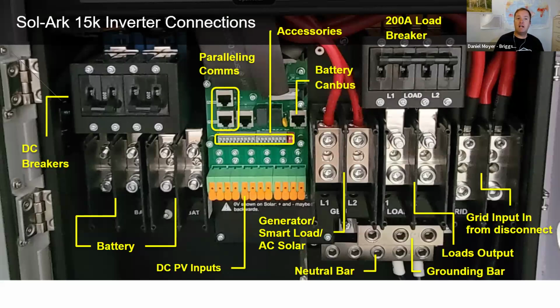On the left-hand side, we have our DC breakers. What's really cool about that Sol-Ark 15K is that we have dual battery inputs, which means that if you're going to have a single stack of our batteries, great, you can bring them in. And if you have 2 stacks of batteries, this is awesome because this avoids having to buy a MidNite Solar combiner or Blue Sea Systems or a Victron combiner. You can bring in both of the stacks of batteries onto these dual lugs and combine them without having to buy an extra piece of equipment.